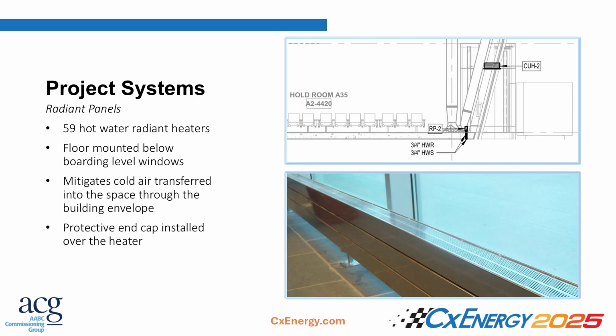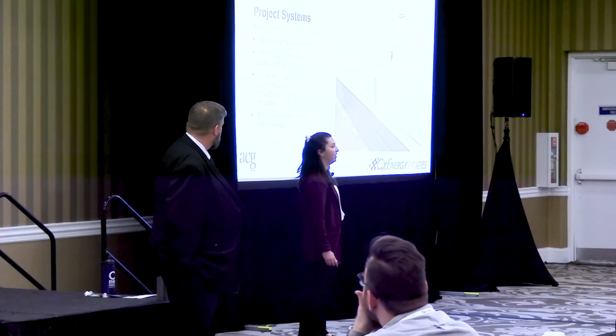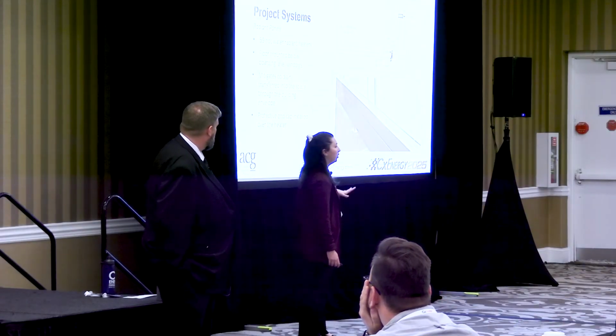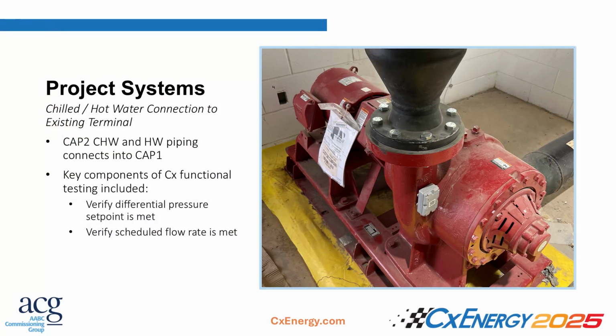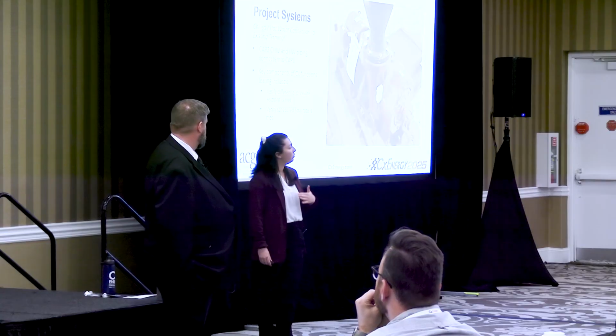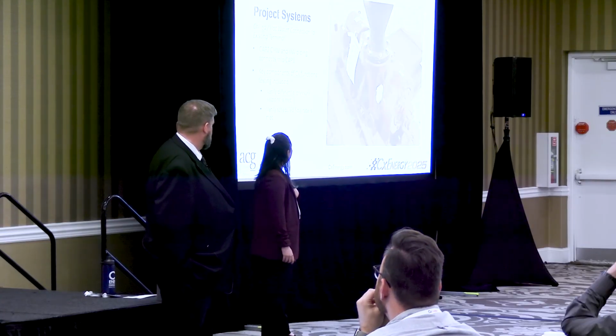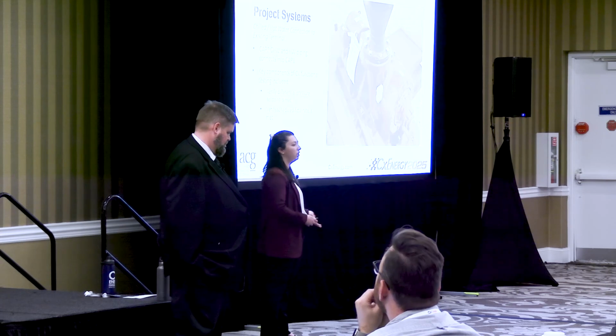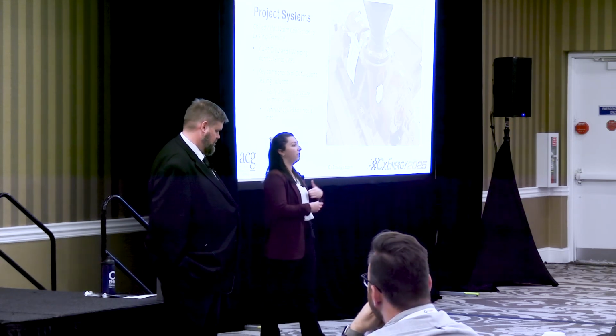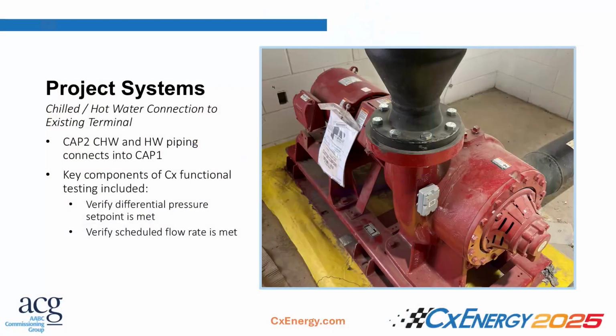And you can see in the top right here, their hot water lines are coming straight from the bottom. So there is that lower ramp level right below it. So that is where those hot water lines come in from. And the hot water is connected to the existing airport system, same for the chilled water. So there was piping from the CAP 1 project that was capped off, and they were able to continue this piping throughout the new CAP 2 expansion. On our project, we did not actually test the chillers and the boilers, but we were more so testing that this new project was functioning well, being tied into that existing system. So making sure that no other areas in this airport were starved of water to their own equipment.